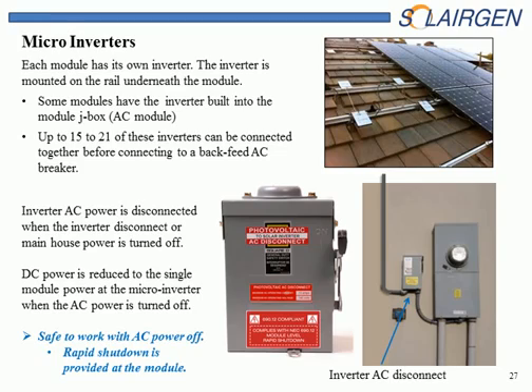But if you see an AC disconnect, you're looking for the type of system that is operating there. You want to see if it's a Solar Edge PV optimized or if it's microinverters. If you see that, you know for a fact that it's safe all the way down to the module. If you don't, you don't know for a fact that the DC circuit is safe. So look for that first.